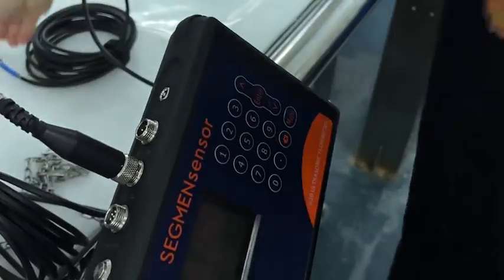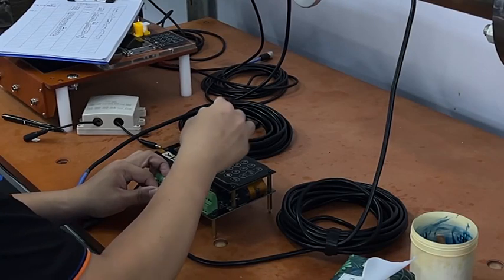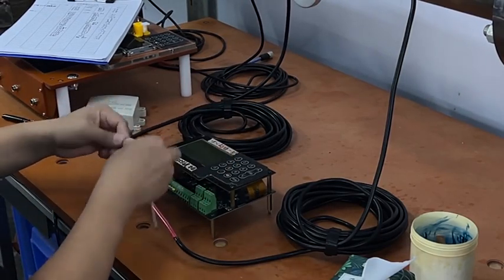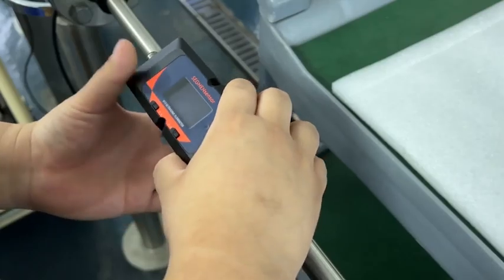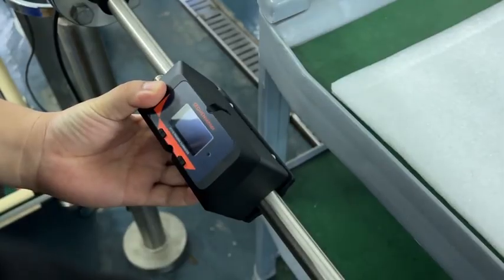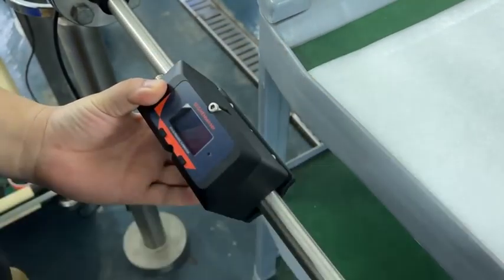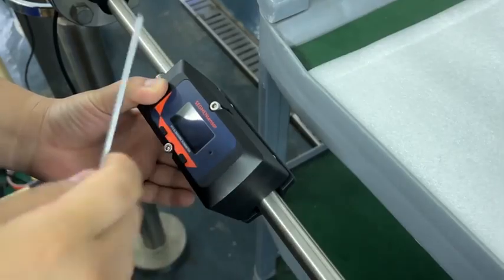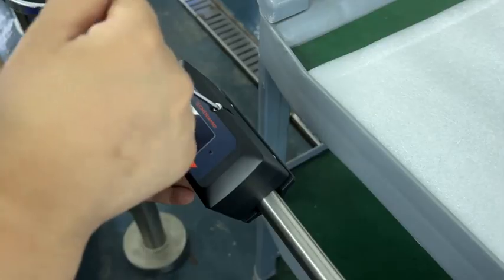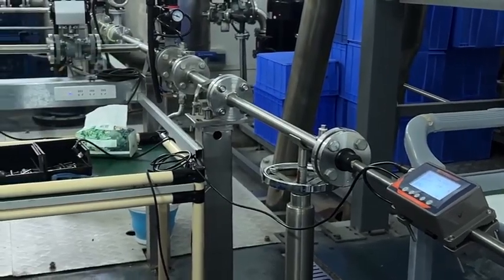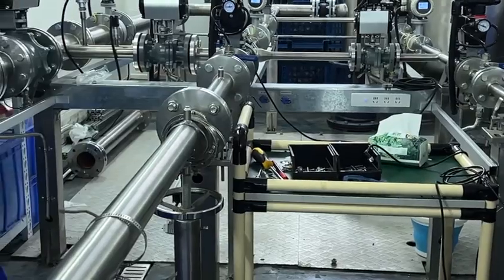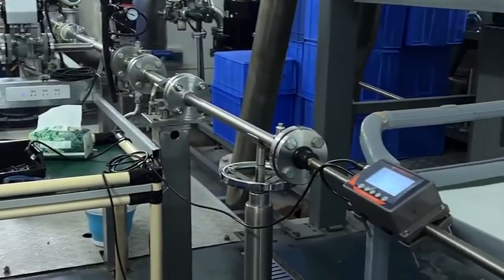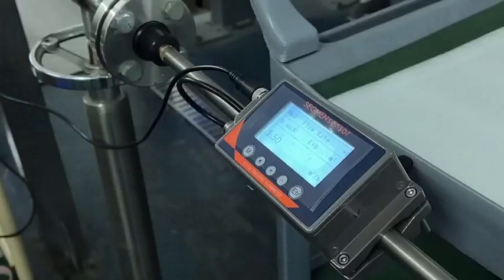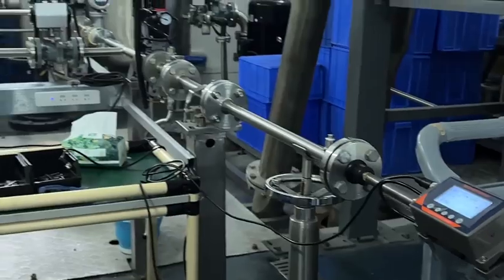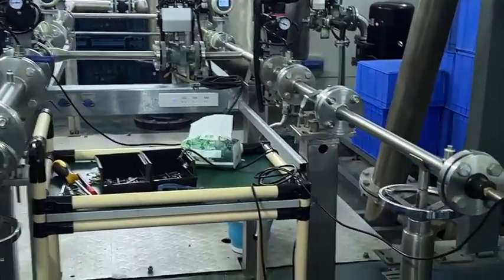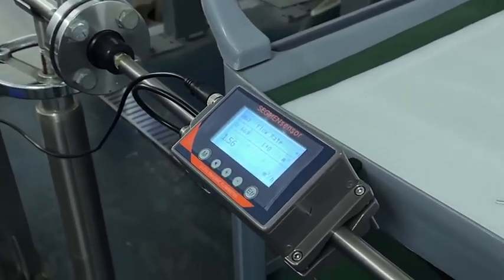The probes are locked into position with the bracket fasteners. Consistent torque ensures both probes maintain the same contact force against the pipe wall. Unequal contact force causes asymmetric signal attenuation and degrades measurement accuracy. Signal cables connect the transducer probes to the transmitter unit. The connectors are IP67 rated, providing protection against dust ingress and temporary water immersion. The transmitter housing itself is rated to IP67, making the complete system suitable for outdoor installation, chemical environments, and industrial washdown areas. Cable routing follows a clean path from the transmitter to each probe. Cables are not kinked or sharply bent near the connector body, as this is the most common cause of premature cable failure in field installations.